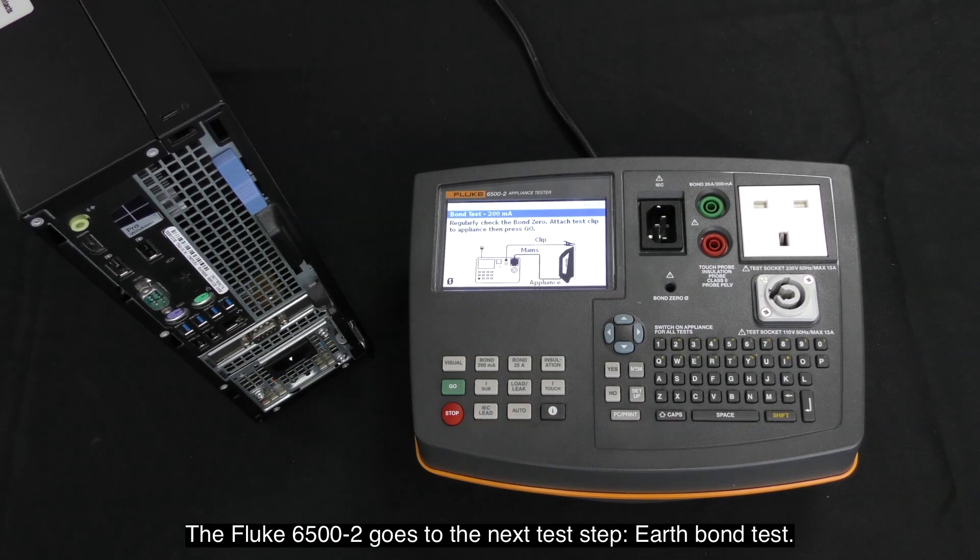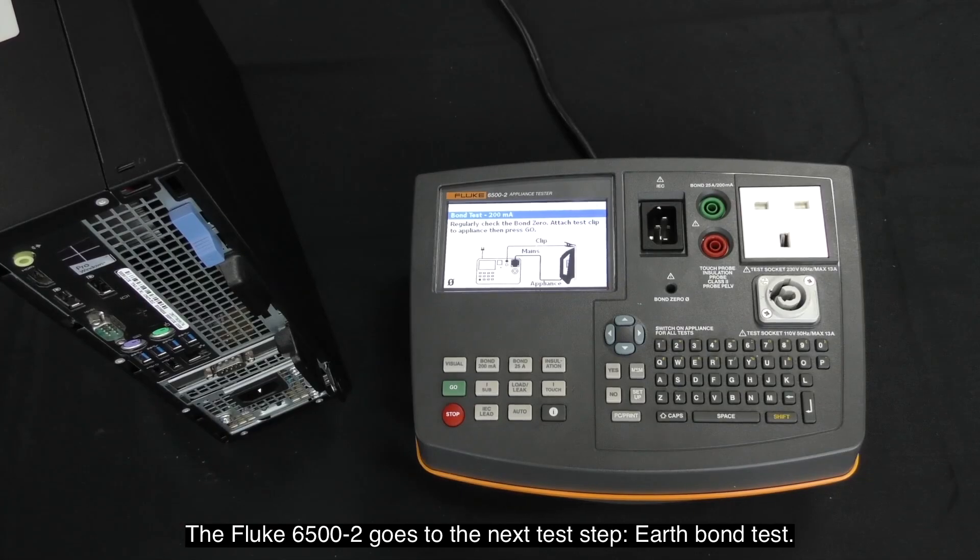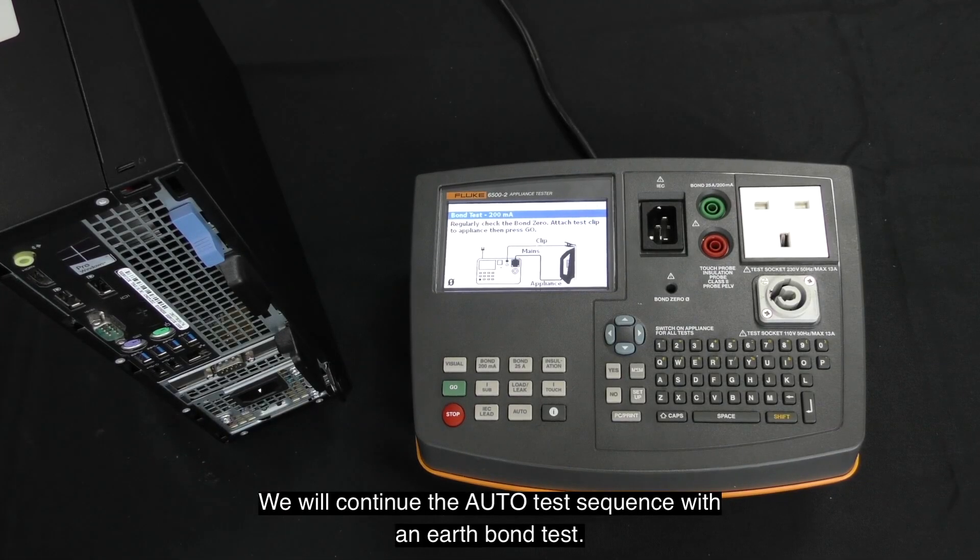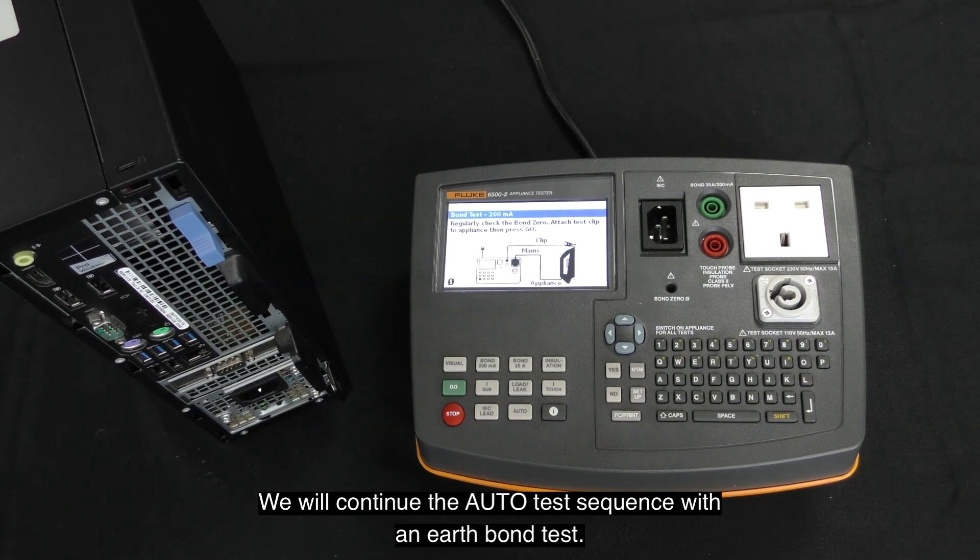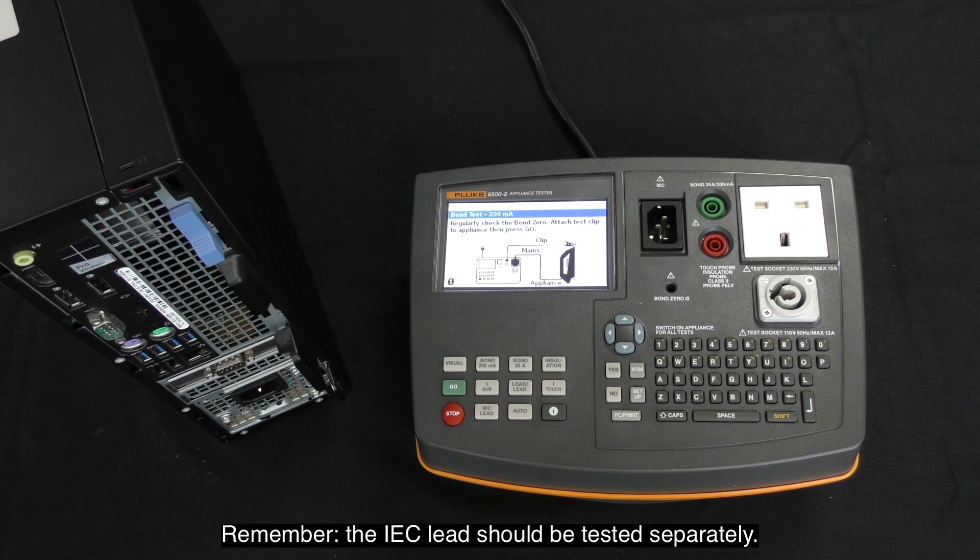Confirm the positive outcome of the test by pressing the S key. The Fluke 6500 Mark II goes to the next step, the earth bond test. We will continue the auto test sequence with an earth bond test. Remember, the IEC lead should be tested separately.